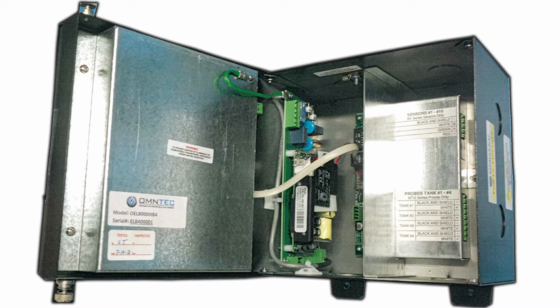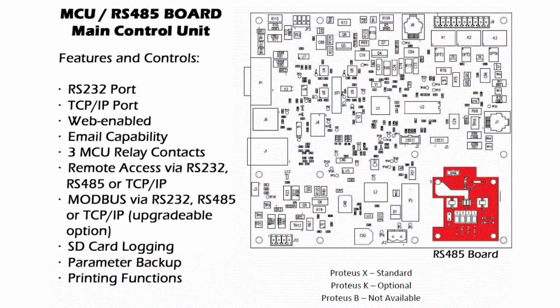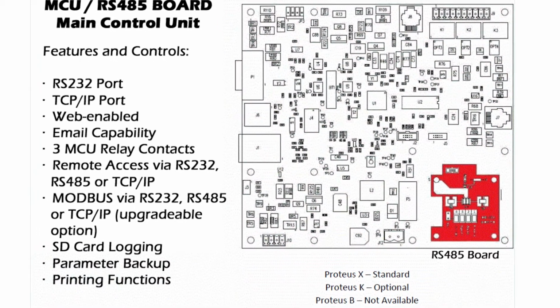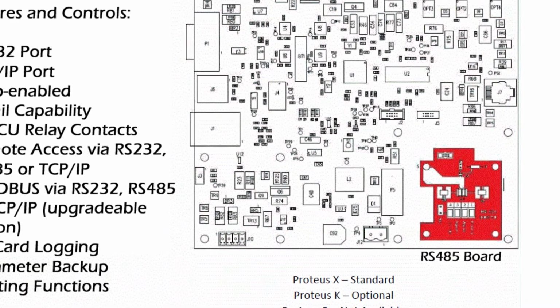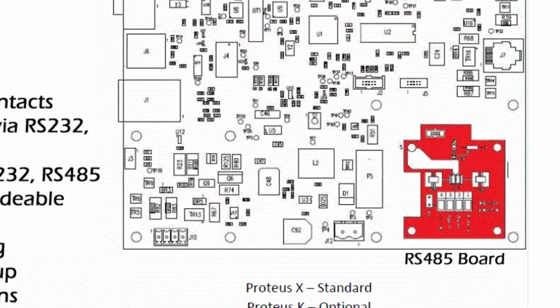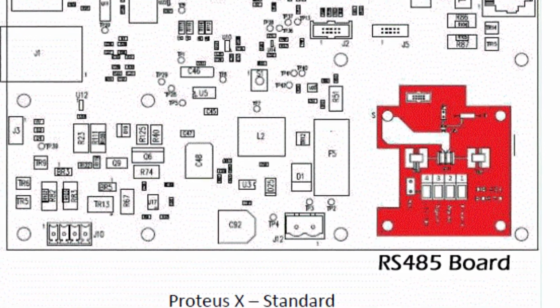Now we will review the various interface boards used in the Proteus line of controllers. The MCU, main control unit, is installed in the Proteus X and Proteus K controllers. It provides the various input-output functions required by the system, as well as the web interface function and optional Modbus protocol. It is the data collection point for log storage and print functions. An RS485 communication board gets mounted on the MCU, which is standard on the Proteus X and optional on the Proteus K.